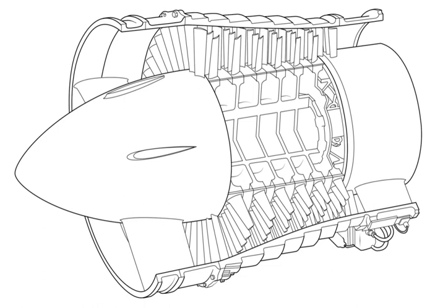The increase in pressure produced by a single stage is limited by the relative velocity between the rotor and the fluid, and the turning and diffusion capabilities of the airfoils. A typical stage in a commercial compressor will produce a pressure increase of between 15% and 60%, pressure ratios of 1.15 to 1.6 at design conditions with a polytropic efficiency in the region of 90 to 95%. To achieve different pressure ratios, axial compressors are designed with different numbers of stages and rotational speeds.